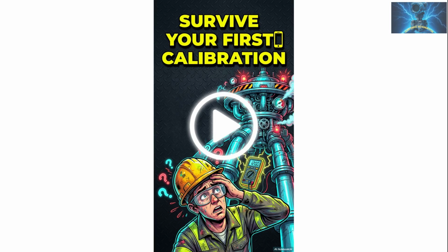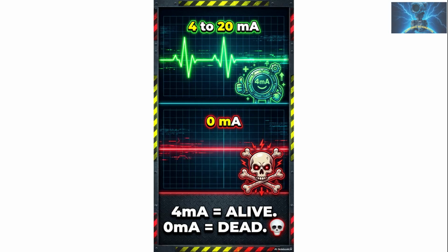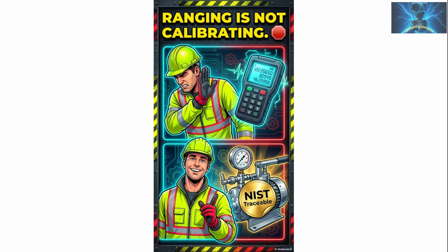First calibration, do not panic. Here is the survival guide that keeps you from chasing ghosts, smoking loops, and looking confused in front of operations. In a 4 to 20 milliamp loop, 4 milliamps means the device is alive at 0%. 0 milliamps usually means dead loop, lost power, bad wiring, or a blown fuse. And no, ranging is not calibrating. Ranging sets the limits. Calibration proves the device is telling the truth against a real, traceable standard.